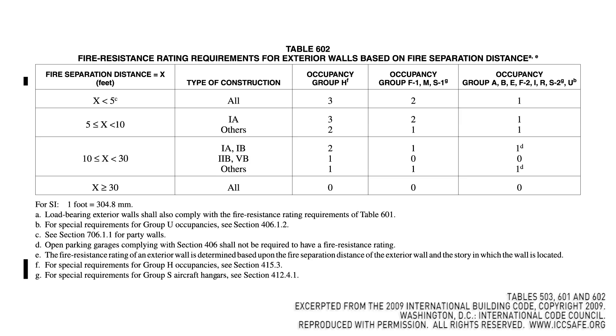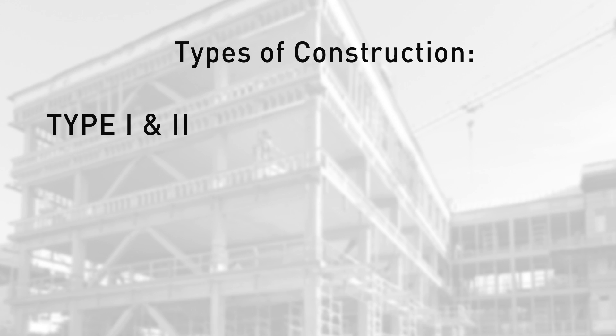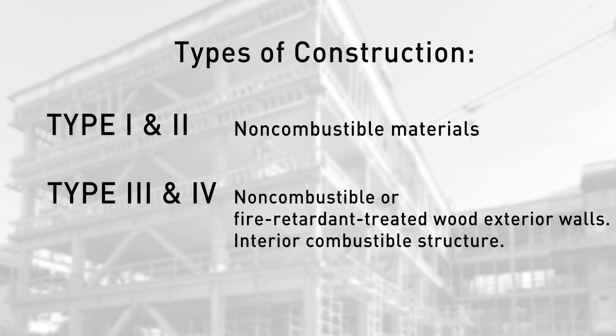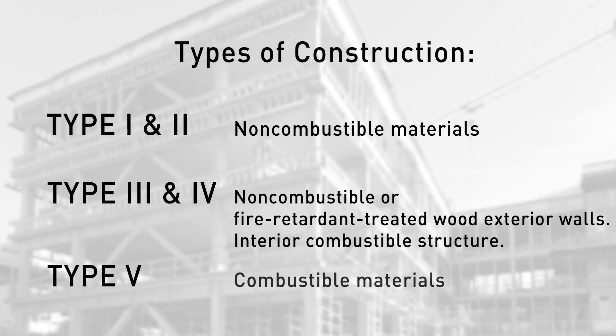There is also Table 602 for the exterior walls — the closer you are to another building, the more requirement you're going to have on the exterior wall. Type 1 and Type 2 are considered typically non-combustible construction. Type 3 and Type 4 are typically non-combustible on the exterior walls and combustible on the interior. Type 5 is any type of material, usually combustible material that's allowed per the Building Code.